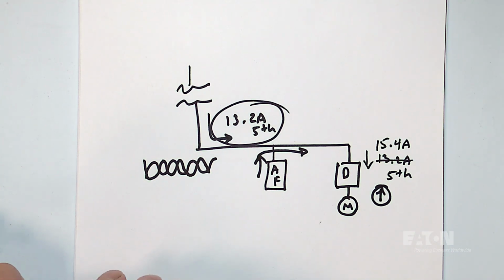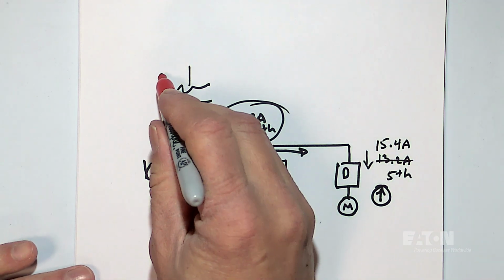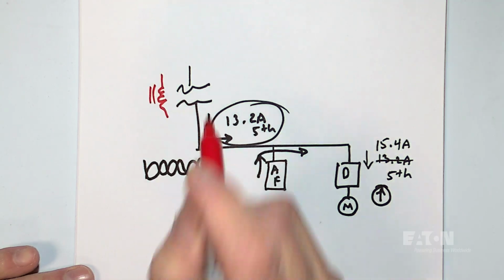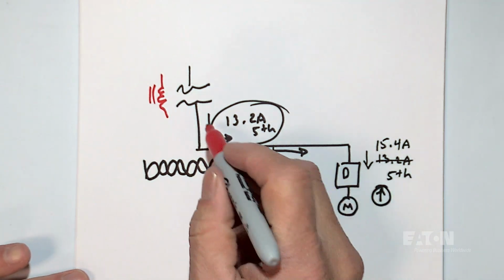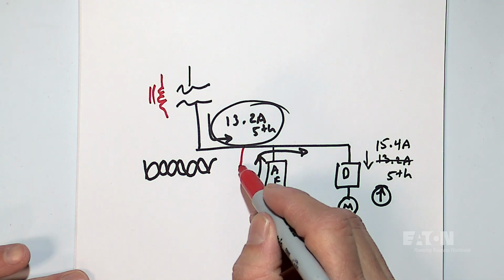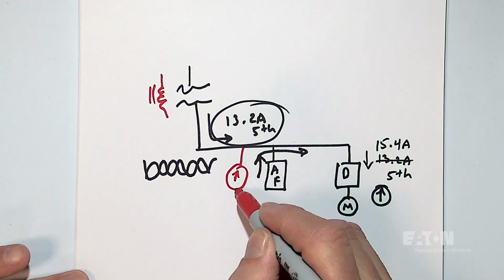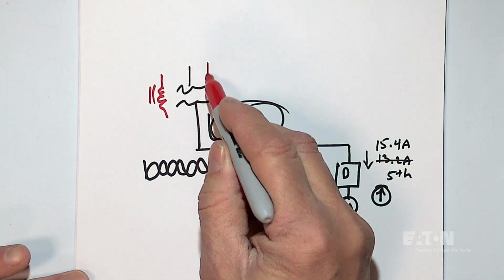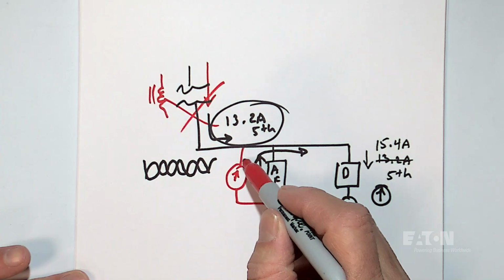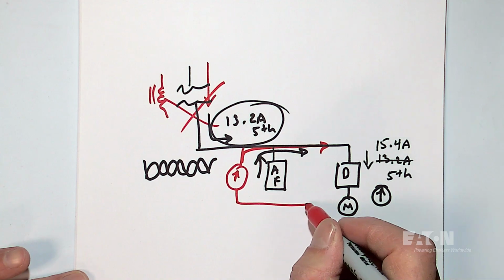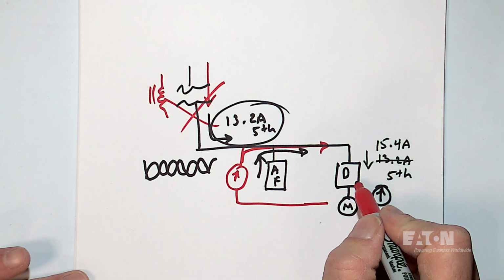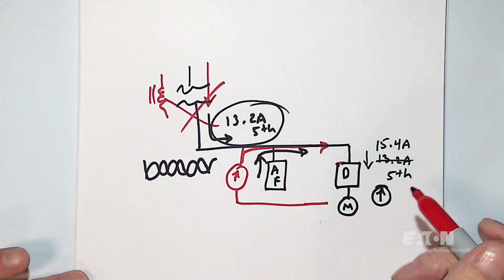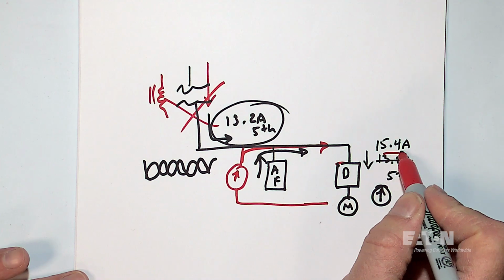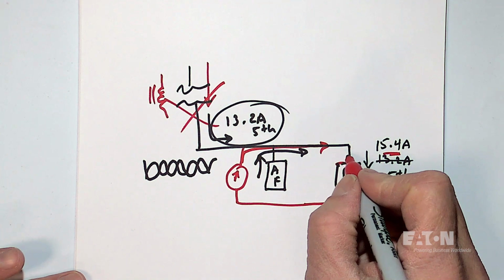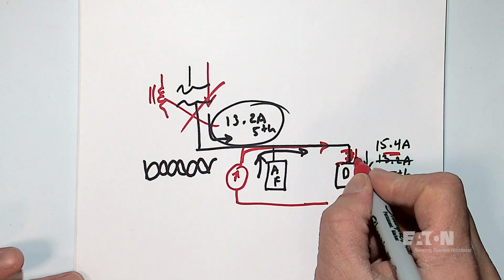Think about it this way. Essentially, we're drawing that harmonic current down through the system and through this thing here, which is a transformer, but essentially a reactor. If I'm shorting out this reactor by putting my source of current right here at the active filter, I don't have to flow that current down through here anymore. I can just have that current flow right to the load. And so therefore, the drive itself is not constricted like a line reactor would do, and so I can actually draw higher current.